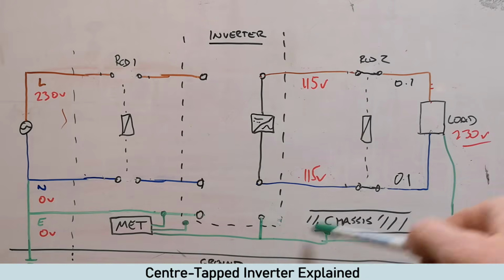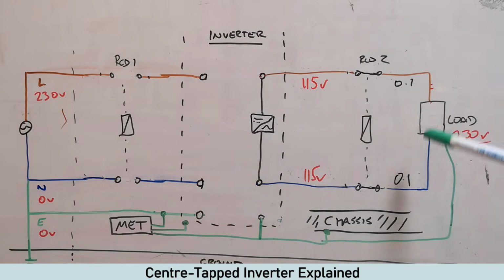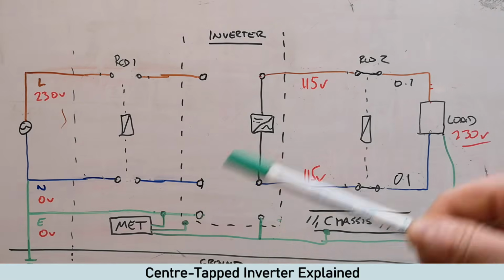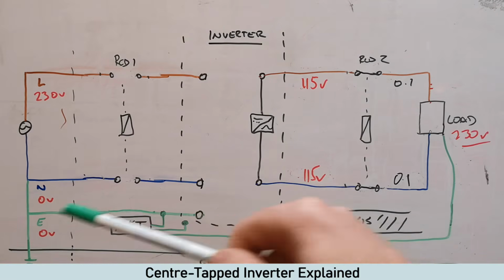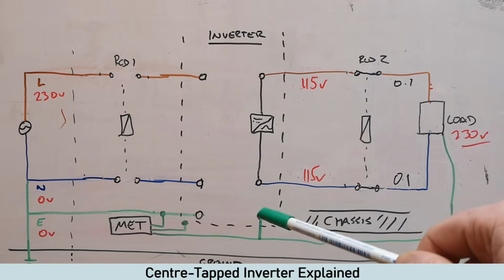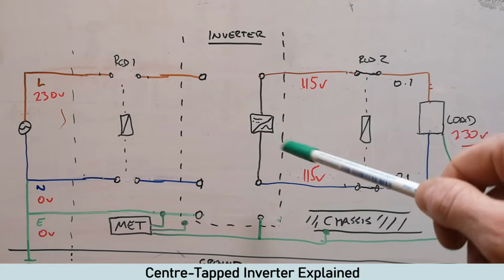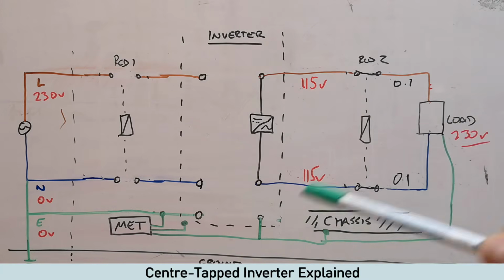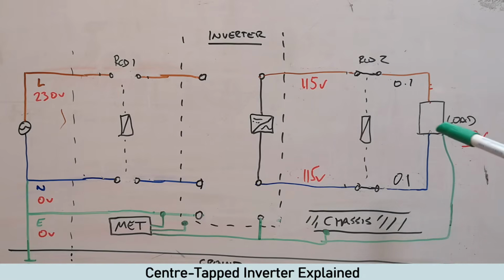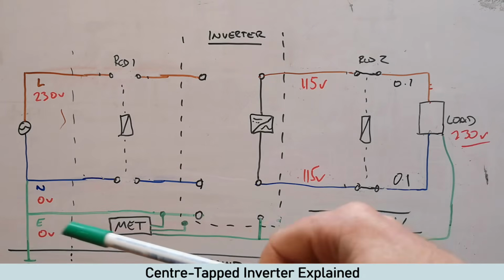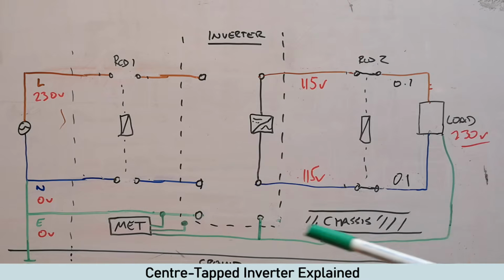Now, what's happening here is this is where we got this floating system. So you can see here there's a neutral to earth bond. Here, there is no neutral to earth bond at all within the unit. So you've got 115, 115. However, you've still got all your earth still linked in. Obviously, that's not changed coming through.